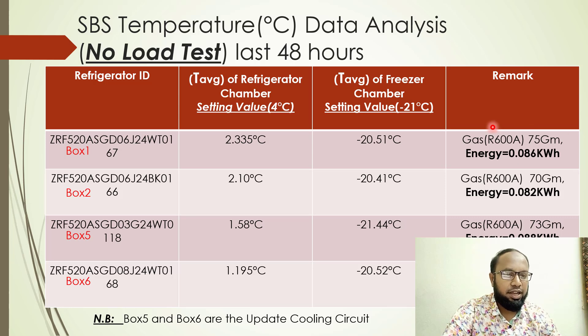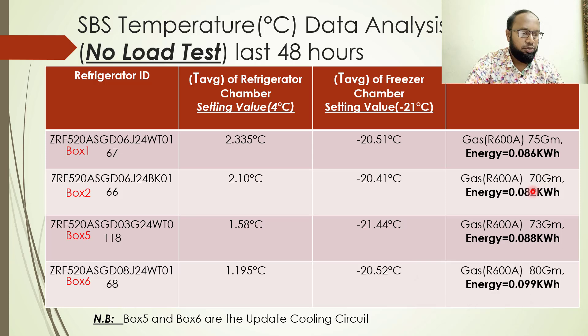After a 48-hour recording period, the results are: the 75-gram refrigerator gives 0.086 kilowatt-hours, the 70-gram refrigerator gives 0.082 kilowatt-hours, the 73-gram refrigerator gives 0.088 kilowatt-hours, and the 80-gram refrigerator gives 0.099 kilowatt-hours. The base refrigerator is the 70-gram gas charge with a compressor power of 0.082 kilowatt-hours, which is the best result.